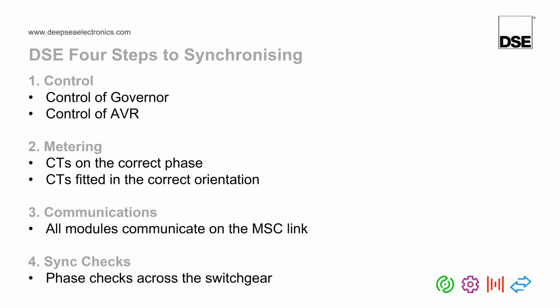So just to go over some of the things that Dave has also mentioned. We'll talk a bit more about this as we go through the presentation, as Dave said. Normally when we're doing the setup of switch 1, switch 2, which is what we're going to be covering next, we're looking for a governor and AVR drive percentage of around 75 to 85%. But in most load sharing applications, the governor and AVR percentage should be less than 10%. I'll cover this a little more later on.